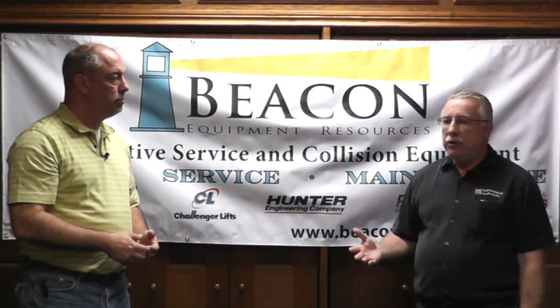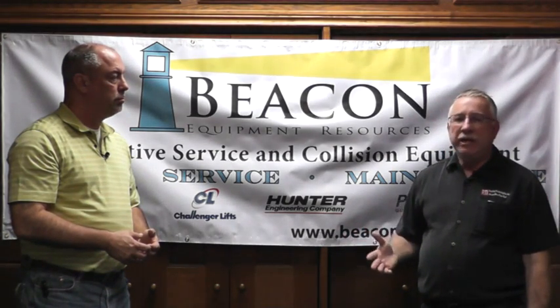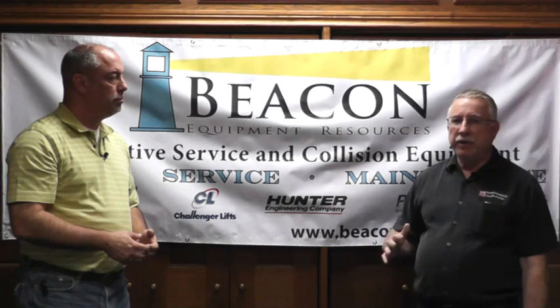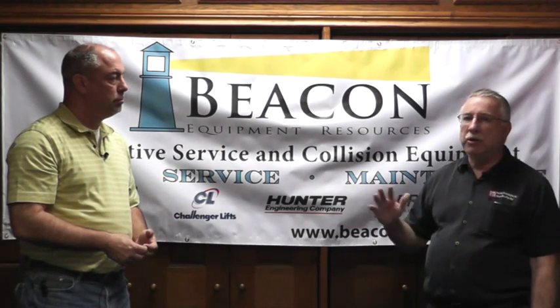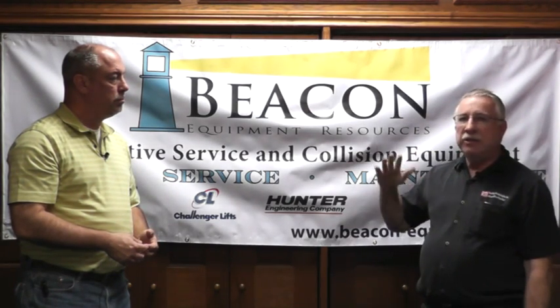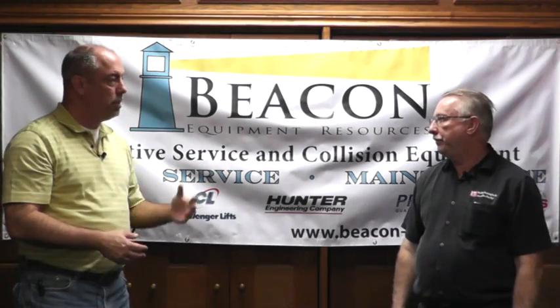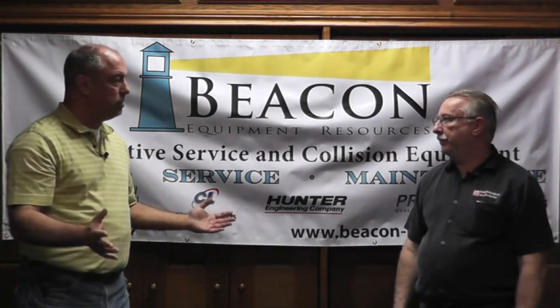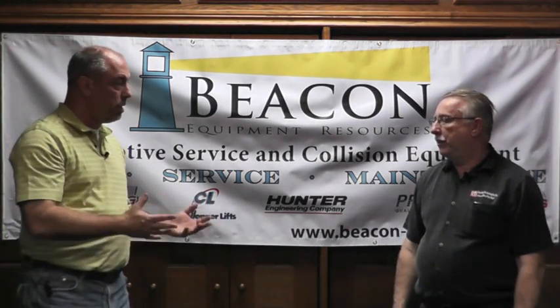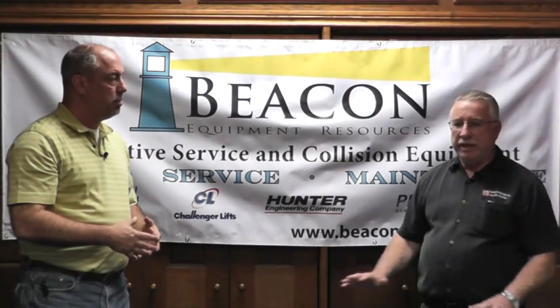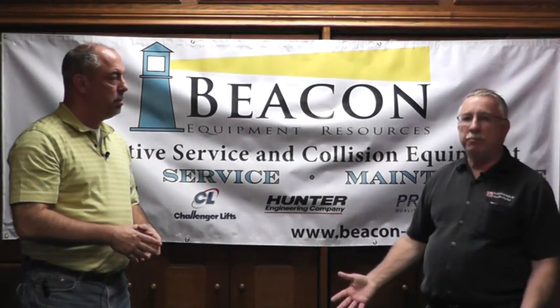And so you're going to get upwards of 93% of the moisture taken out, and you're going to have a relative humidity, or compressed air humidity, of about 18 to 28%. And that's a good humidity range for most applications in an automotive service or body shop. Right. For a shop, that's good. That's great for everything in the shop except for the painting area.